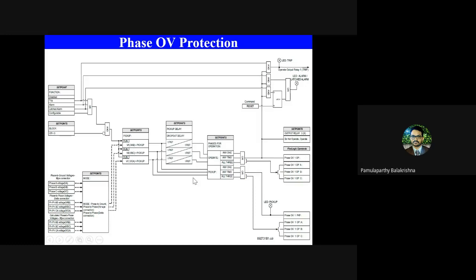Like that, every protection logic design is defined in terms of how the protection function has to behave, what signals are required for that function, and what logic it has to execute, whether there is a timer available or not before taking the decision, on what basis I need to take the decision, and how I need to inform the operator. After pickup, what do I have to inform, and after operate, what do I have to inform. When I say operate, the action is to either trip the breaker, alarm the operator, or do a latched alarm, or do an action defined by the user, like both trip and alarm, or all three combinations, or anything else the user says. All of those will be executed.